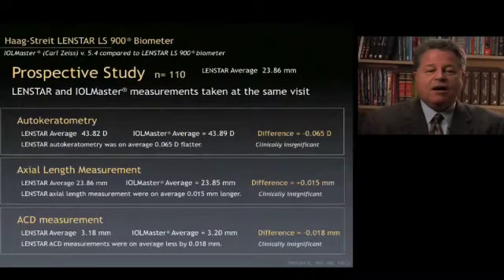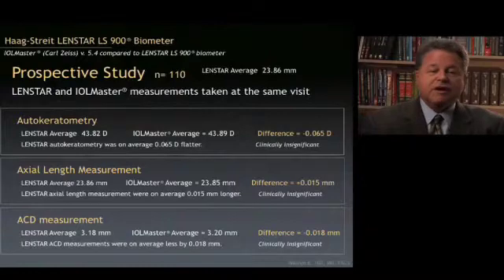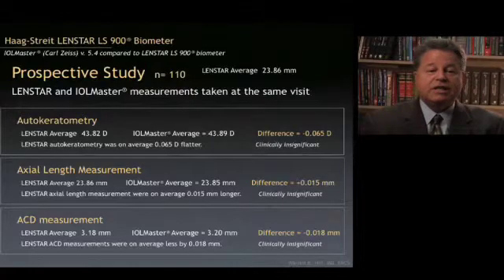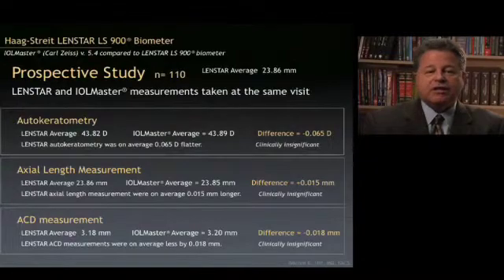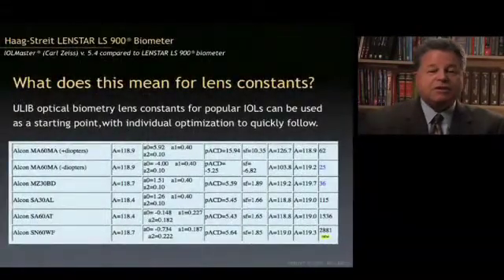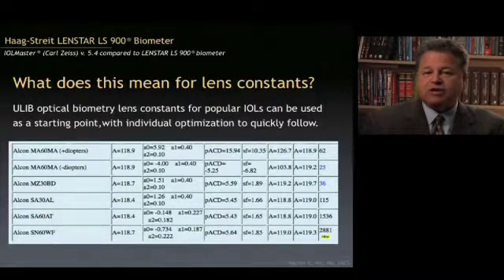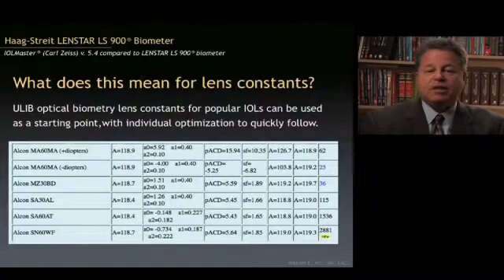The question comes up a lot: how close is this to the IOL Master, and can I use lens constants developed for other forms of optical biometry? In our office we did a prospective study of 110 eyes measured by both the LenStar and IOL Master at the same visit. We found that auto-keratometry, axial length measurement, and anterior chamber depth differed by such a small amount that they were clinically insignificant. This means lens constants developed for other forms of optical biometry can be used as a starting point for the LenStar, and the operator would then quickly do individual optimization.